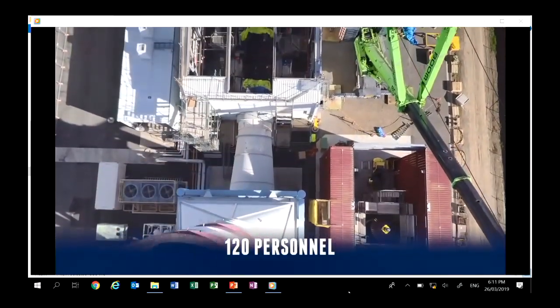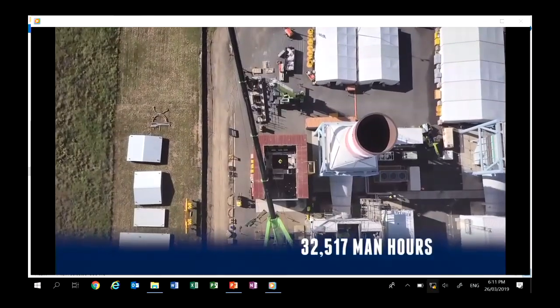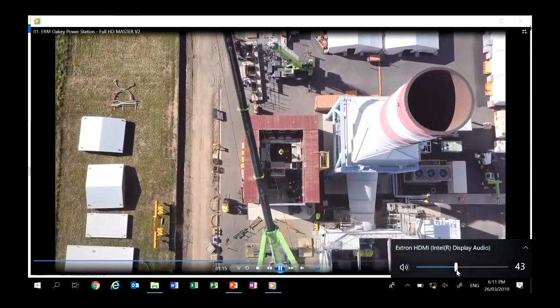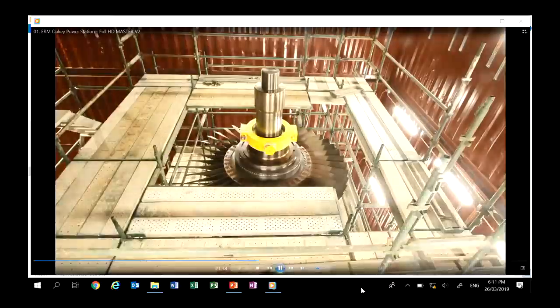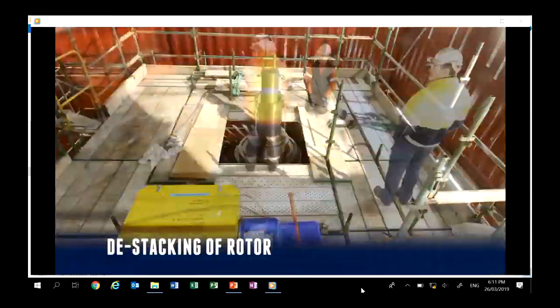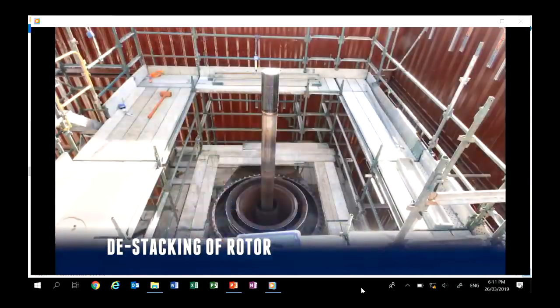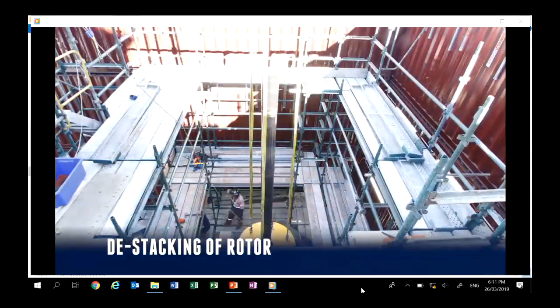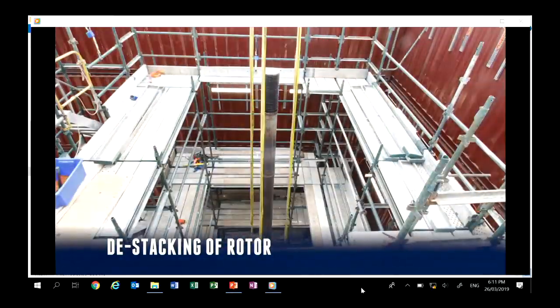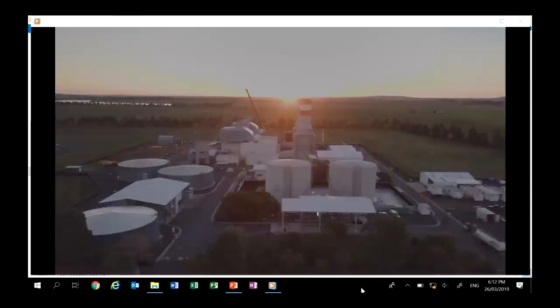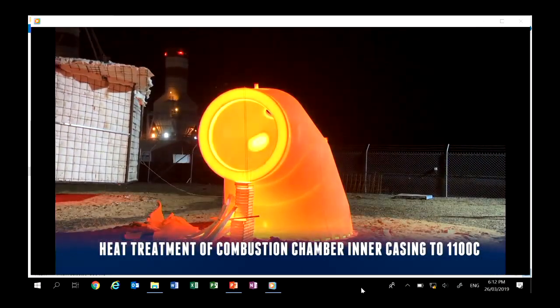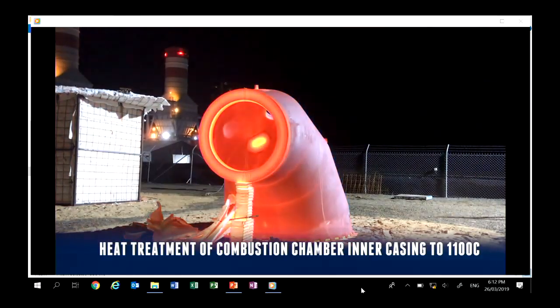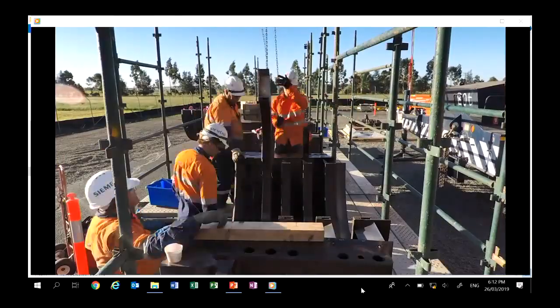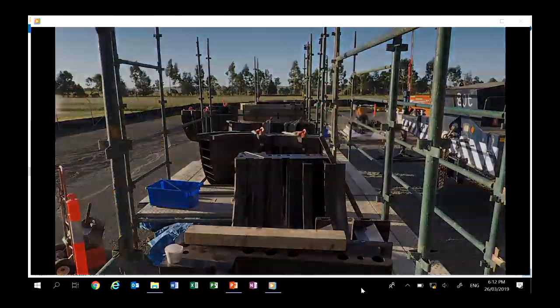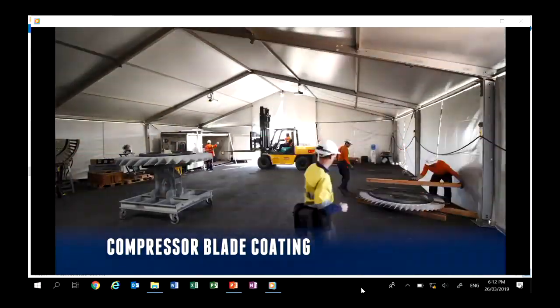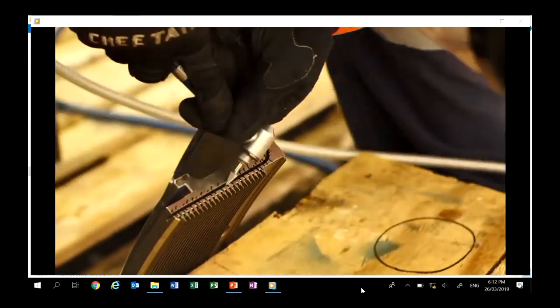Okay, and then the rotor is destacked so as to allow us to deblade the turbine. So it all comes apart. Then various components like these mixing chambers have to be heat treated in order to normalise the metallurgy, so it's good for another 10 years of operation. We do that on site. We recoat the compressor blades, so they do deteriorate somewhat even though they're in fresh air.